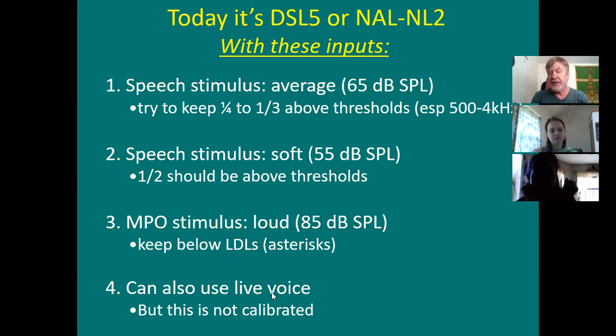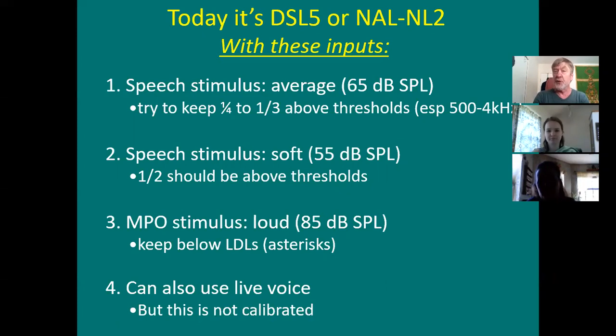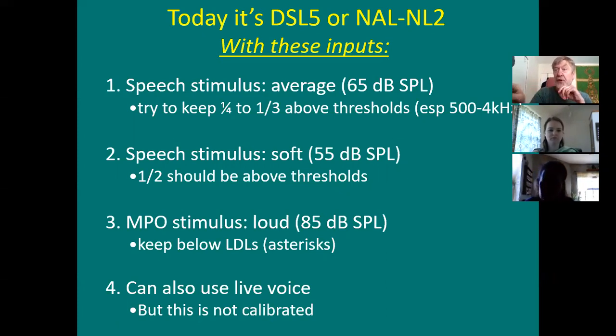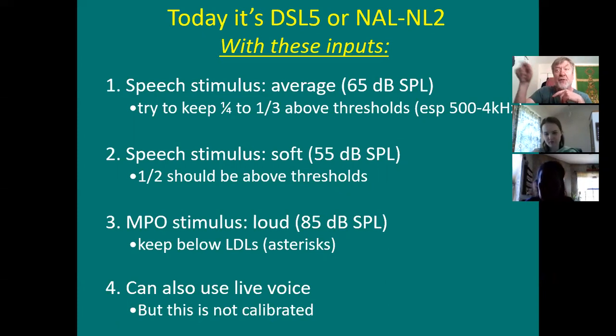Some people also use live voice of a spouse or a loved one — that's not a bad idea. It makes things homey, but the problem is it's not calibrated. If you want to draw in the spouse and make connections, you can have him or her talk at the husband wearing the hearing aids, then unaided — watch the outputs fall below the thresholds — and then aided at a normal loudness level, watch the outputs go above the thresholds. It actually draws in the client and makes the whole process a union of the relationship, because hearing loss involves connections. But the problem is the speech from the spouse isn't exactly the same as the rainbow passage or what they have on other real ear systems.